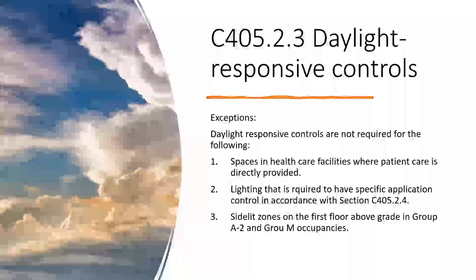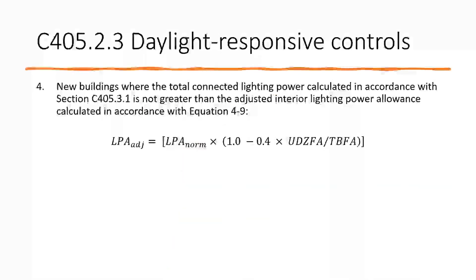Exceptions: daylight responsive controls are not required in healthcare facilities where patient care is directly provided, lighting that is required to have specific application controls per section 405.2.4, and side-lit zones on the first floor above grade for A2 or group M occupancies. Also excepted are new buildings where the total connected lighting power calculated in accordance with section 405.3.1 is not greater than the adjusted interior lighting power allowance calculated in accordance with Equation 4-9.